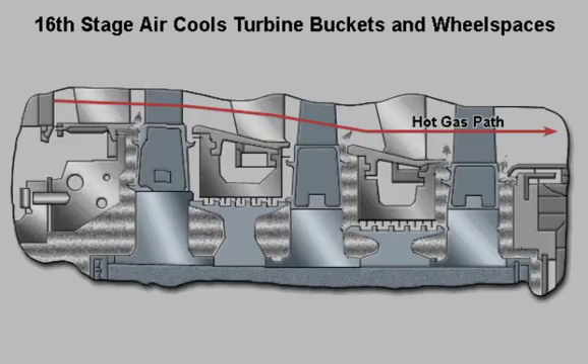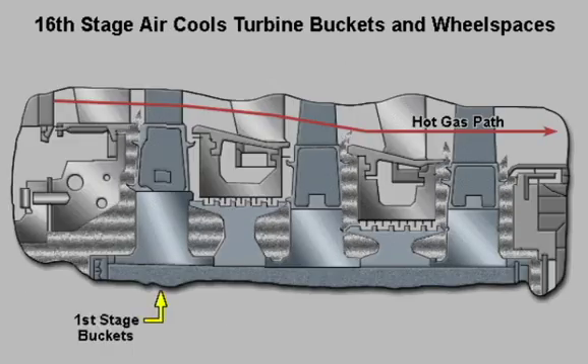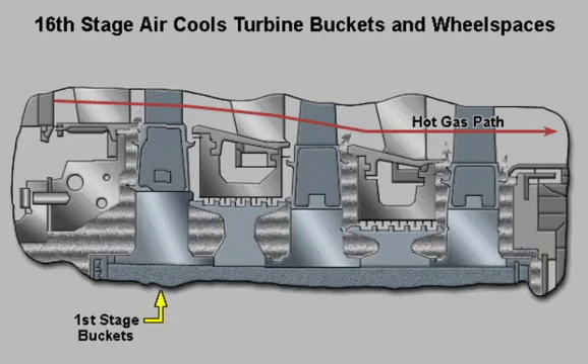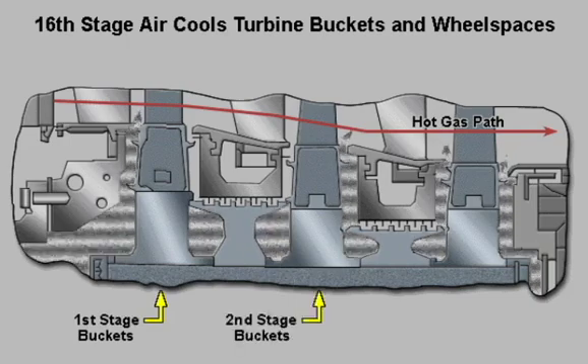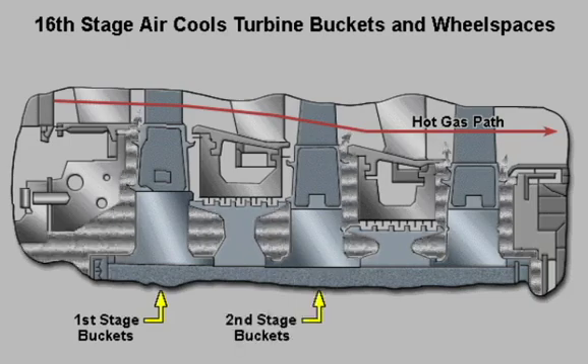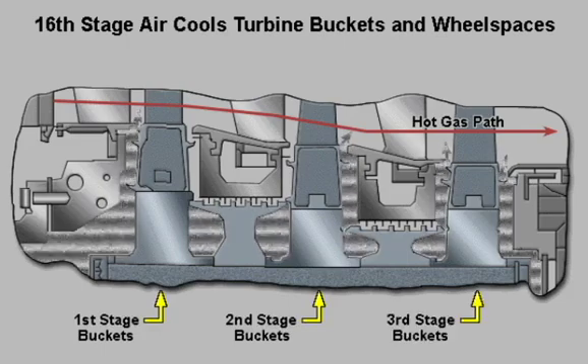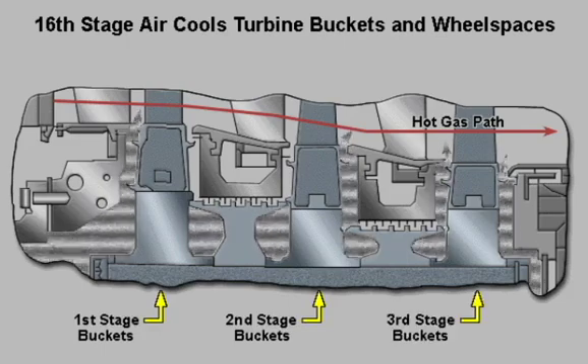In the turbine section, the extracted air cools the first and second stage turbine buckets. Cooling air also flows through the second stage aft side wheel space and the third stage forward side wheel space.